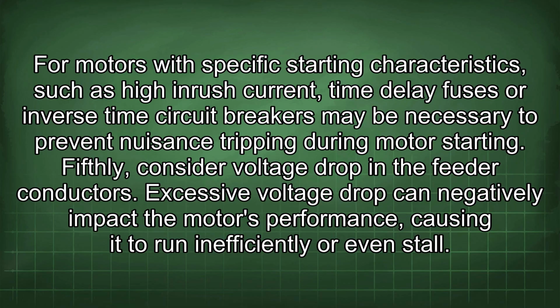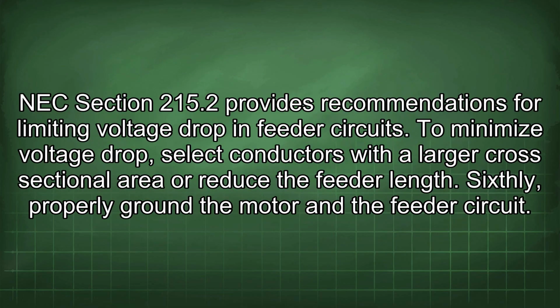Fifthly, consider voltage drop in the feeder conductors. Excessive voltage drop can negatively impact the motor's performance, causing it to run inefficiently or even stall. NEC section 215.2 provides recommendations for limiting voltage drop in feeder circuits. To minimize voltage drop, select conductors with a larger cross-sectional area or reduce the feeder length.